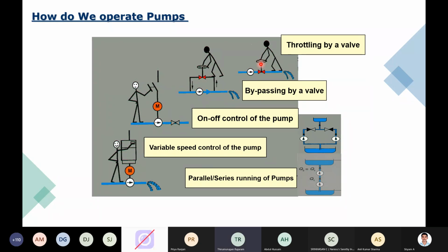This has been practiced for very many years, and even in very old industries you can still see the throttle valve getting opened or closed based upon the flow required at site. Bypassing by a valve is a situation where, whenever there is excess flow, people bypass it with a valve. That flow goes back to a tank, but the pump still develops for its 100% requirement. For example, with 100% flow from the discharge, you allow 80% to your system and that 20% is wastage. It comes back to your tank, but energy consumed is for 100%. So that is also an energy killing situation.